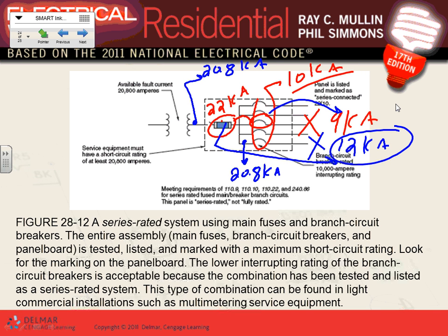Any questions, you guys, about the series rated versus fully rated? And the most important thing is the dollars. The bottom line, who cares? The same panel can be fully rated or series rated design. What's going to decide is what circuit breaker you put in that panel, and it will decide how much money you're going to spend for this panel.